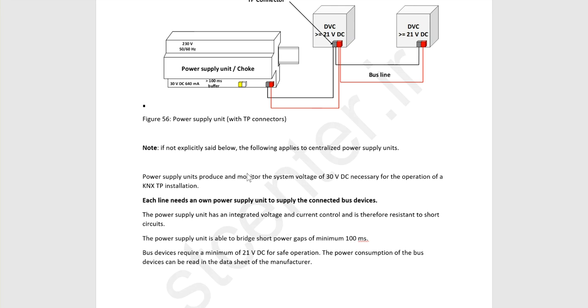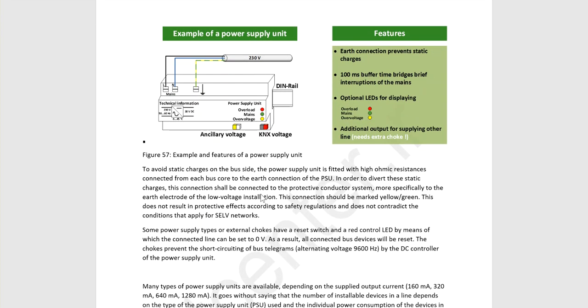Always there is some LED on a power supply unit. It provides us some key information. First of all, in a power supply unit, there is the only place that you should connect to the earth. Earth connection prevents static charging. Because of static charges, we should always connect the power supply unit to the earth. The 100 millisecond buffer time bridges brief interruptions of the mains, so you can make the shortcut by pressing the reset. There is an optional LED on a power supply unit.